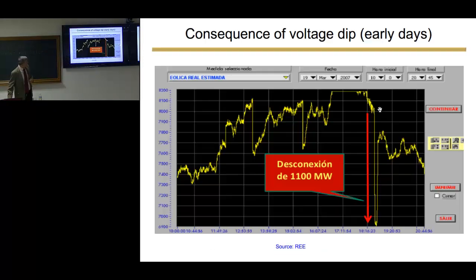This happened many years ago, in 2007, at the beginning of the era of wind energy, when wind generators were not as sophisticated as today. They were not able to withstand this voltage, and there was a sudden disconnection of 1 gigawatt of wind energy. Because of this, the grid codes were reinforced and made more exigent, and now in Spain, all wind energy farms must withstand voltage dips according to the grid code.